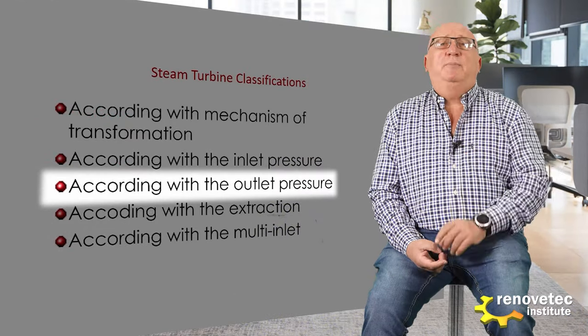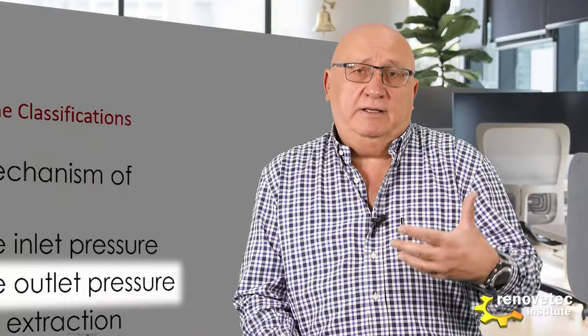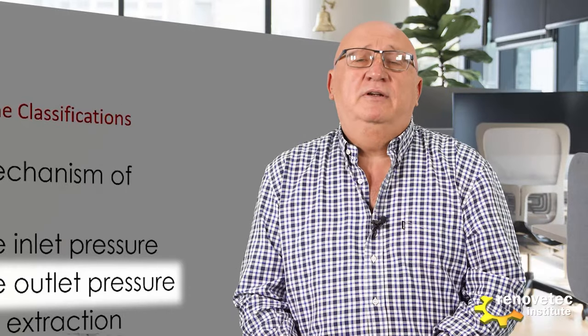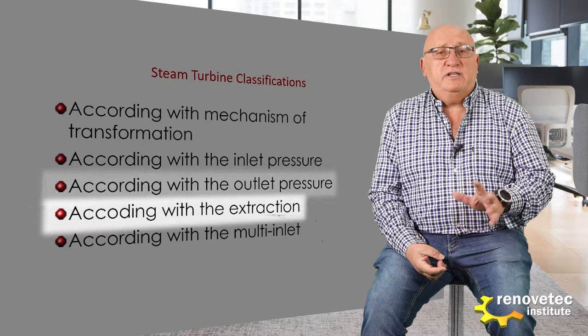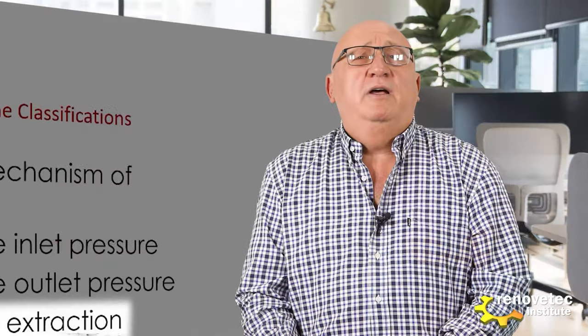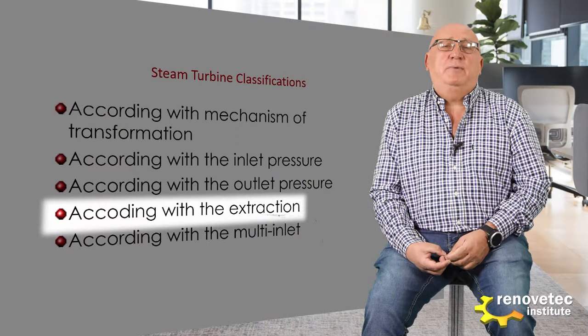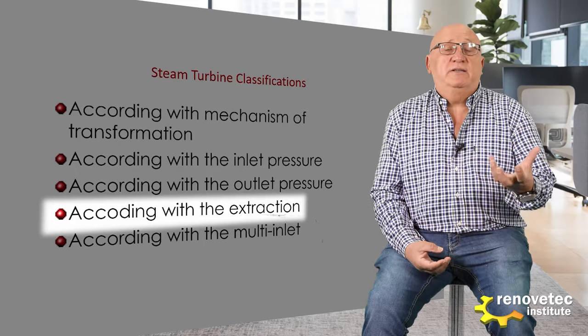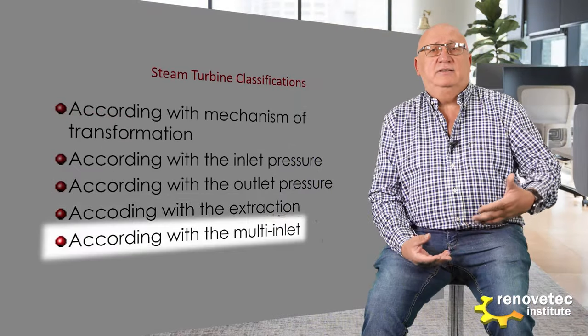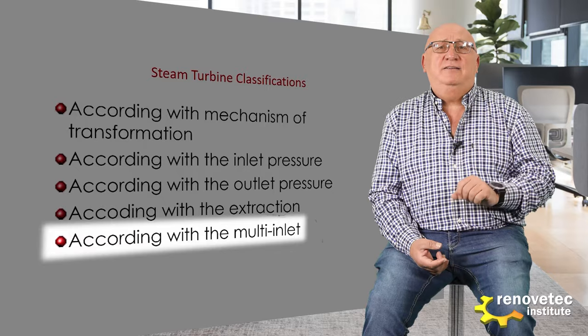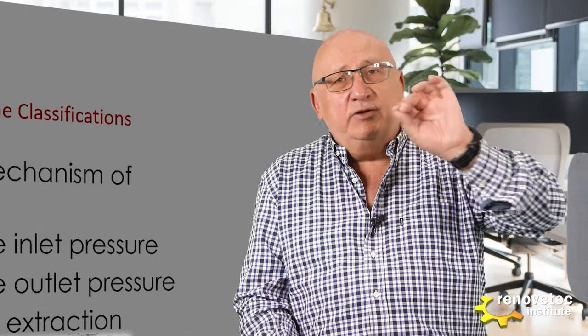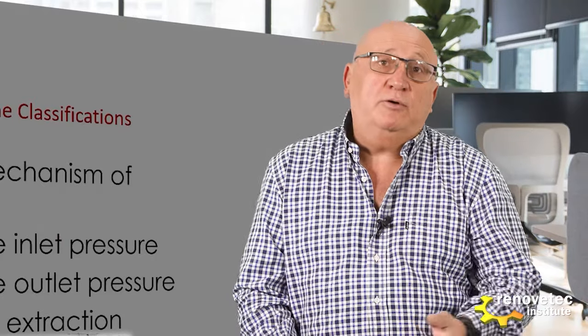The third classification is according to the outlet pressure. We have two types of turbines: back pressure turbine, where the pressure at the outlet is more than one bar, and condensing turbines, where the pressure is under one bar. According to the possibility to have an extraction, we have turbines with extraction and turbines without extraction. Extraction means the possibility to extract some part of the steam flow to use for another purpose. According to the possibility to have multi-inlet, we divide turbines between those that have an intermediate inlet in the flow path and those that do not.